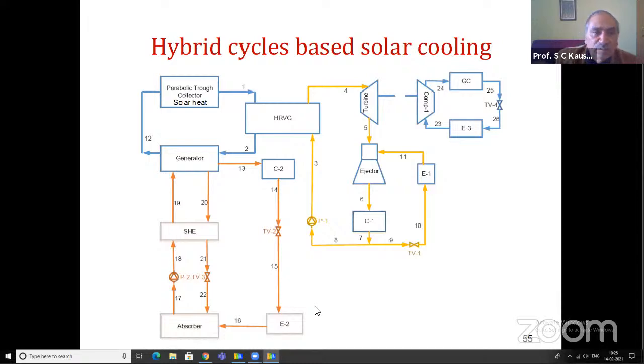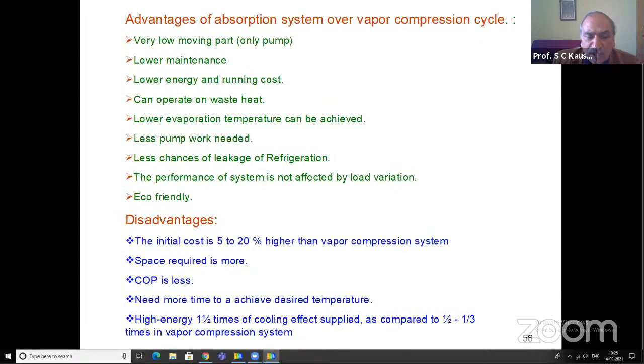Now let us see what are the major advantages of the vapor absorption systems as compared to the vapor compression systems. You can say very few moving parts, lower maintenance, lower energy and running cost, can operate on waste heat, lower evaporation temperature, less pump work, less chances of leakage of refrigerant. The performance of the system is not affected by load variation, and these systems are eco-friendly.